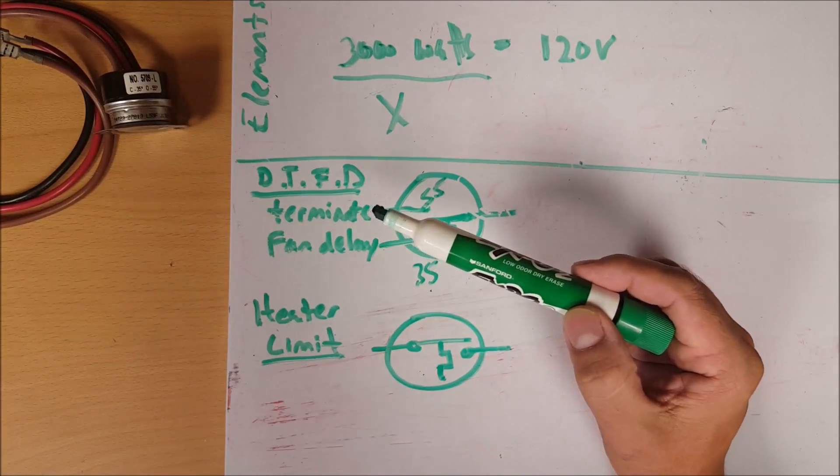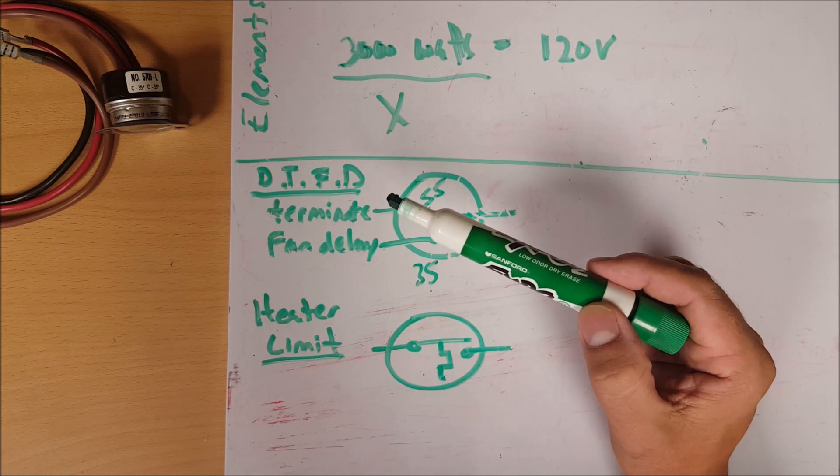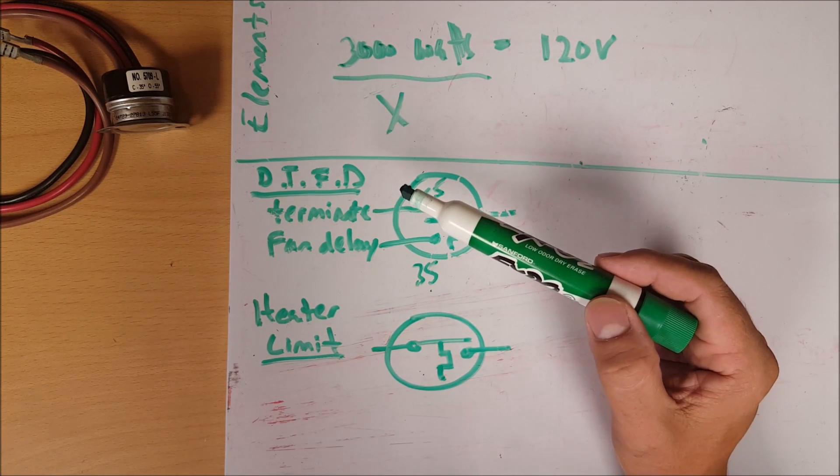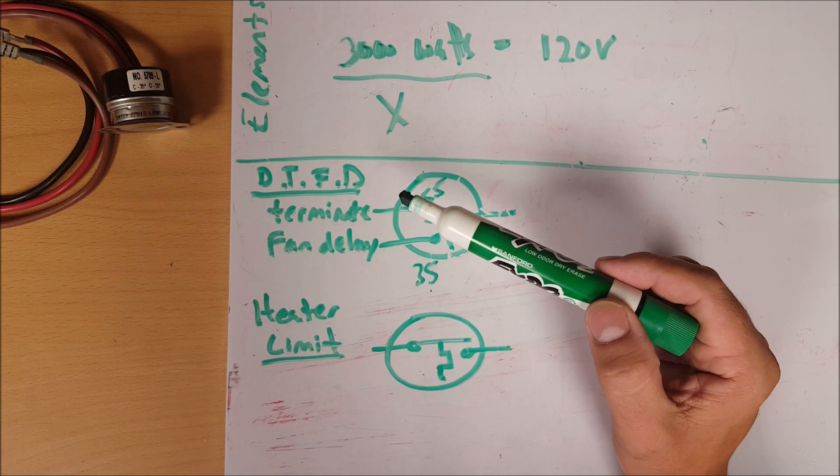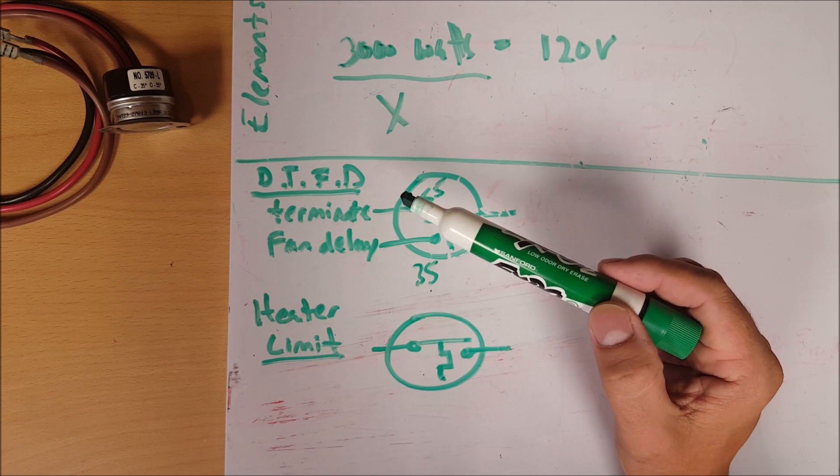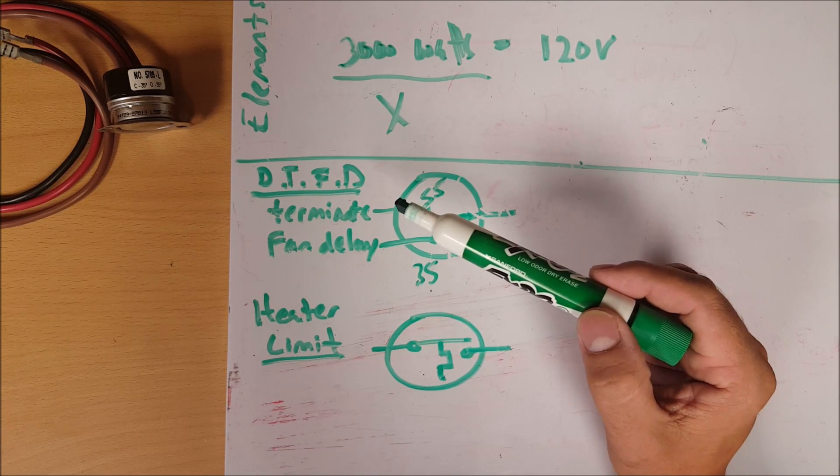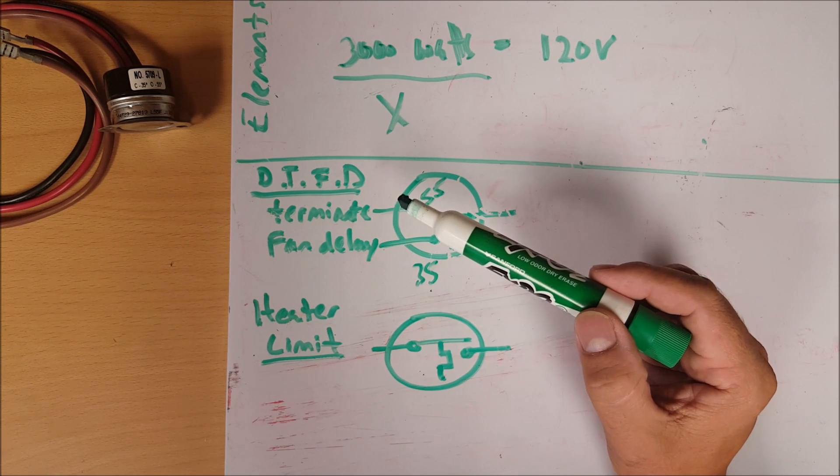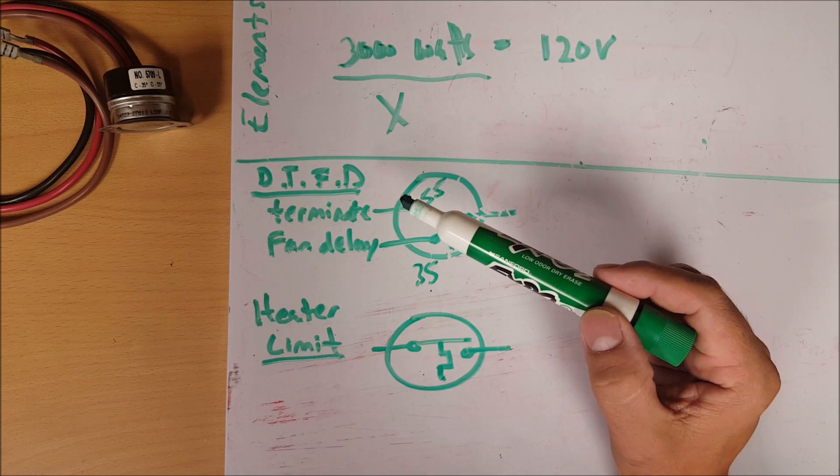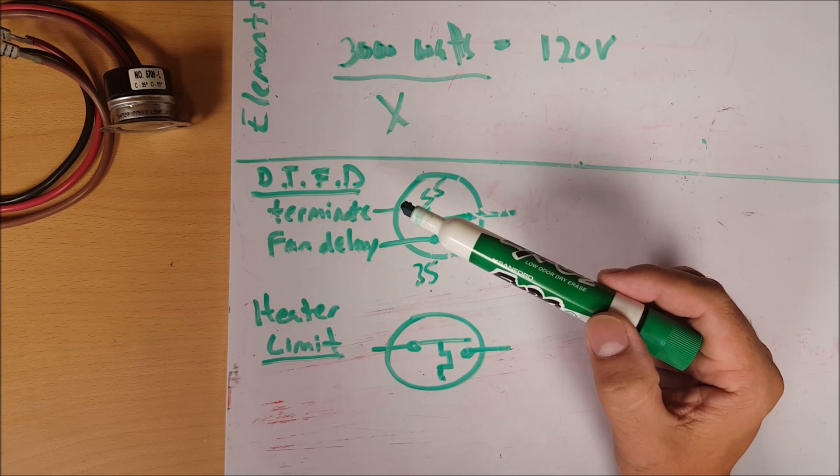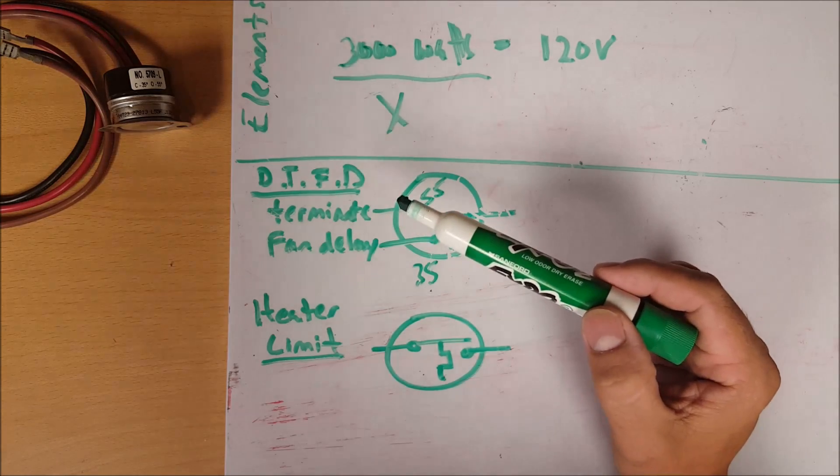Really there's two reasons for delaying your fans. Number one is if you just came out of defrost you have a bunch of water draining or dripping into your drain pan, and hopefully by the time these fans come on all that water has gone down the drain. If the fans were to come on right away, all that water and residual moisture is going to be sprayed into your box.